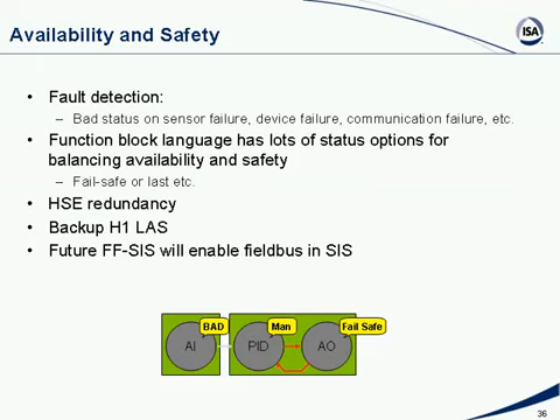Instead of having a redundant interface card, what they do is put a backup link active scheduler, or backup LAS, in one or more of the field devices. So if the interface card fails, as long as you have power supply, control in the field can continue uninterrupted. You get great availability even without redundant interface cards — that's a pretty neat feature.